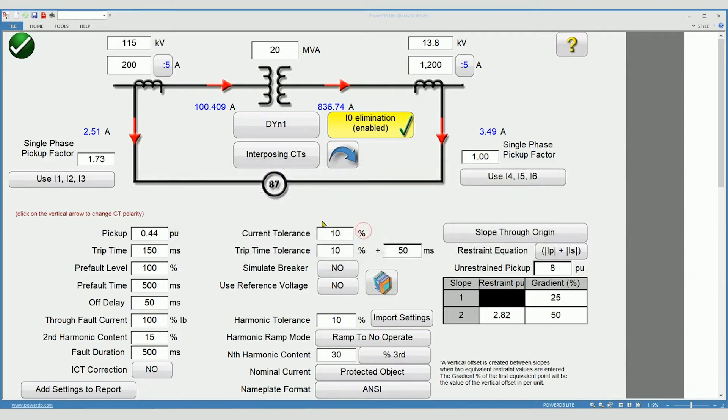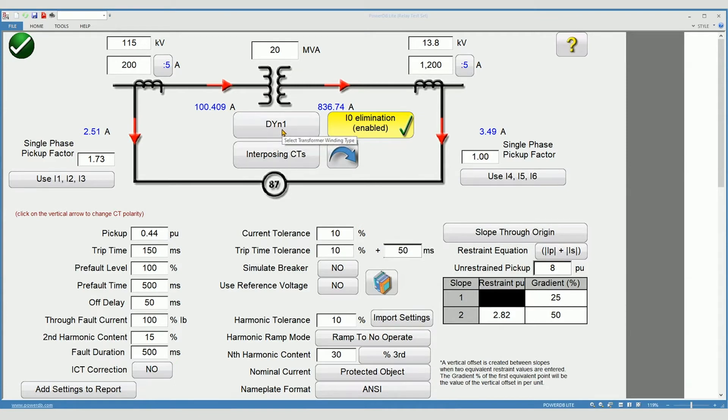Notice the message. Please ensure the automatically computed single-phase pickup factors match the factors specified in your relay manual. We'll talk about this more in just a moment. We've selected a DYN1 transformer. This is the most common substation transformer in North America.